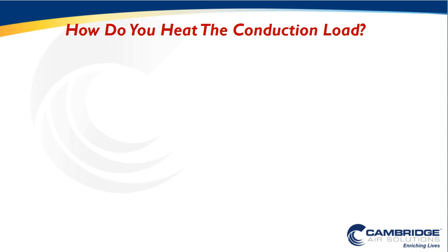Well, one method that is often deployed is we add some element of indirect fired recirculation systems. We may either add additional unit heaters, some kind of indirect fired packaged rooftop, maybe an indirect fired air turnover system, or other kinds of indirect fired infrared systems that require the recirculation of indoor air with an indirect fired system. However, what you'll know is that all of those systems are going to be limited from an energy efficiency perspective by the flue losses inside the heat exchanger.